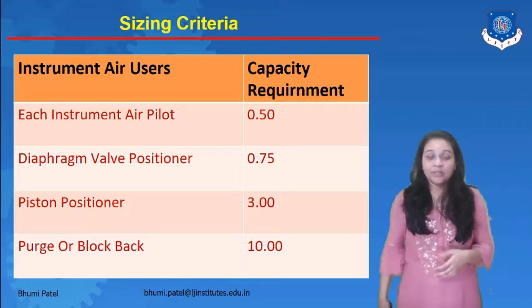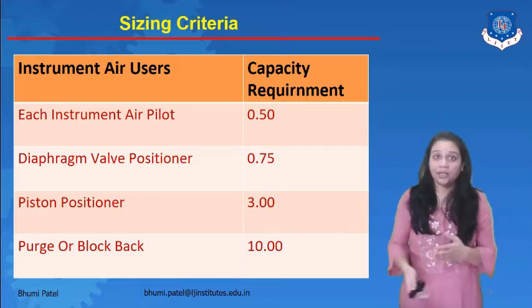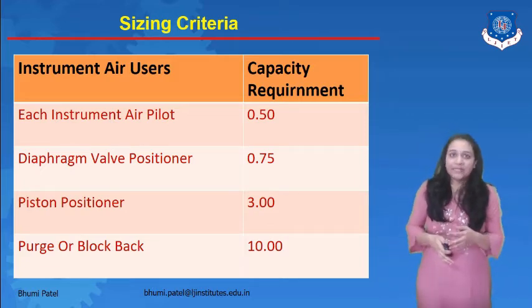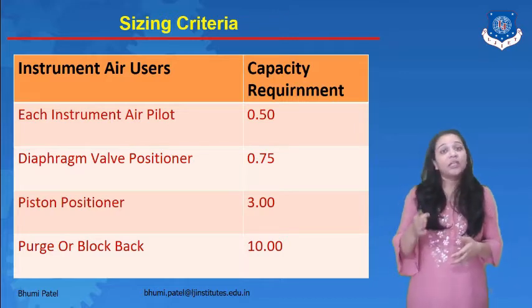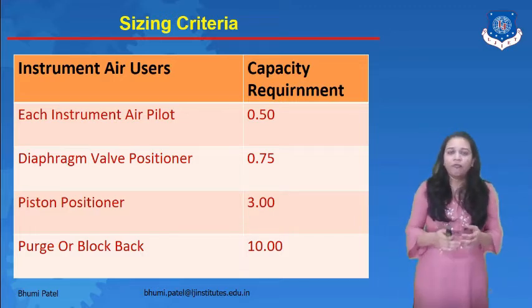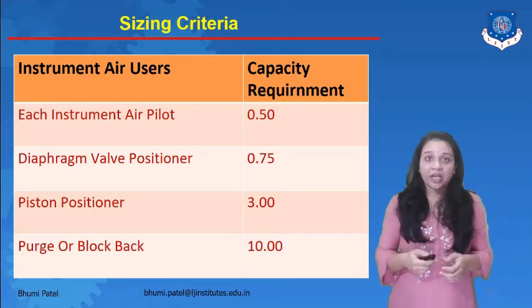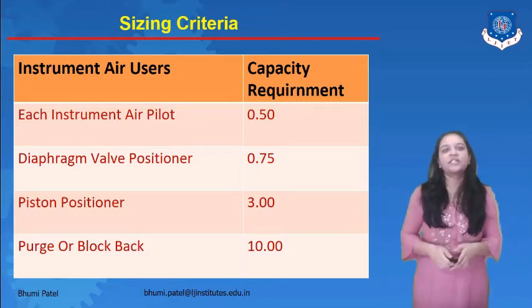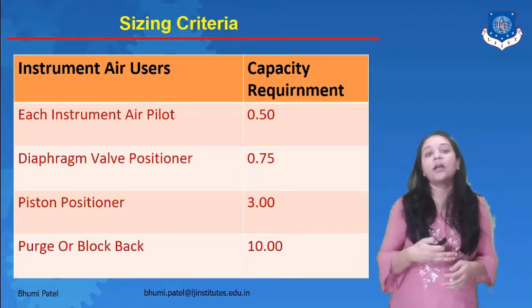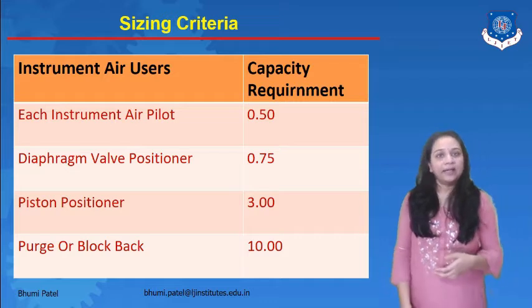For a piston positioner, generally used in mechanical systems where a cylinder and piston mechanism is employed, the capacity requirement is 3.00. If there is a purge or blowback system with multiple pipe connections in the same instrument system, the capacity requirement for that instrument air user is 10.00. So depending upon the application, system, and connections, different capacity values are required for the sizing criteria.